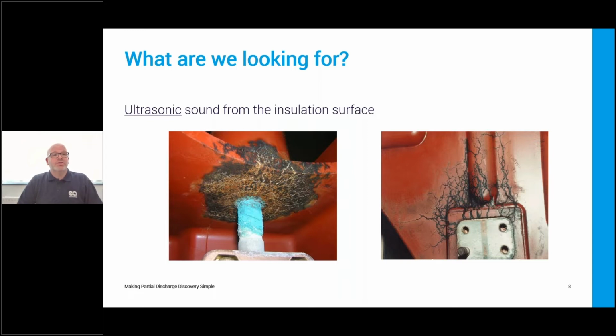And then back to surface discharge, or ultrasonic discharge. A couple of pictures there show the results of some pretty high levels of surface PD. When we're looking for ultrasonic or surface PD, we're essentially listening for the sound of PD on the insulation surface. Now, PD has quite a unique sound, as I'm sure many of you have heard. It's an irregular crackling sound, quite distinctive from white noise. Severe cases of PD can even be heard without the use of an UltraTEV or headphones, just with a human ear. Again, probably time to leave the substation if you can hear it just with your own ears.